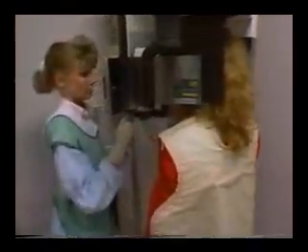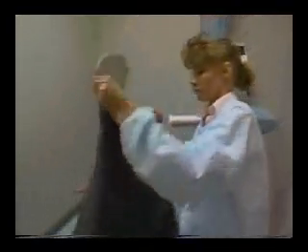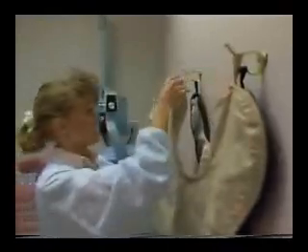The aprons should be placed on the patient before the first exposure and left on until the last X-ray film is exposed. The apron should cover the chest, the throat, and reproductive areas of the patient. The aprons should not be stored by folding. Cracks may result from the bending of the lead insert, which might allow radiation to leak through. The lead aprons should be checked for cracks about once every 3 months.